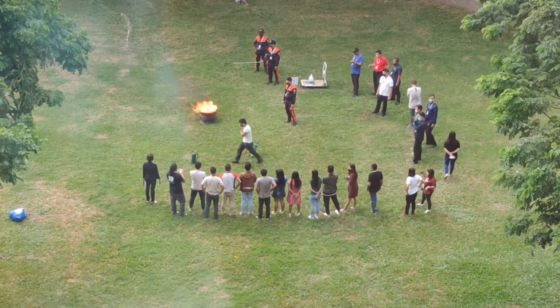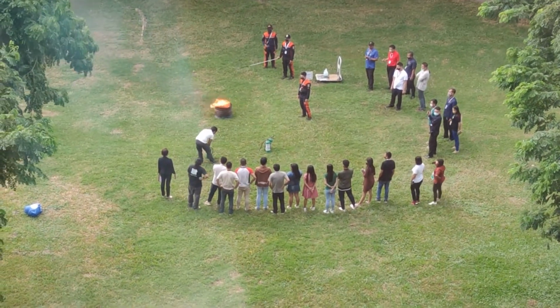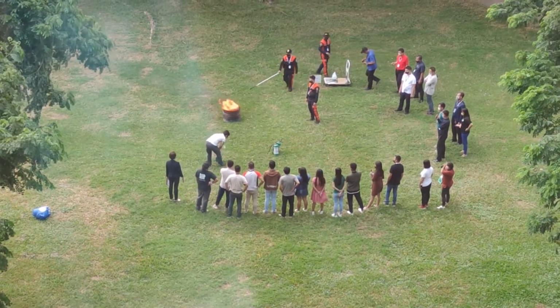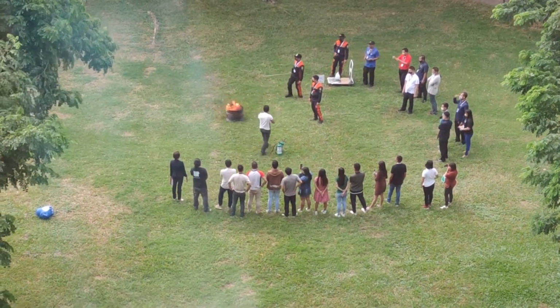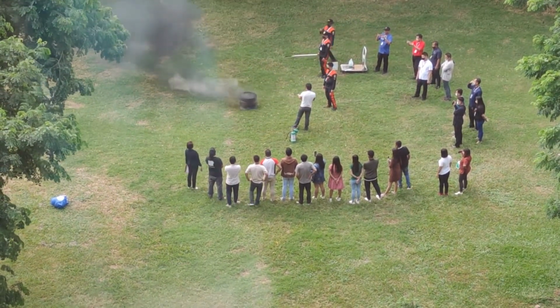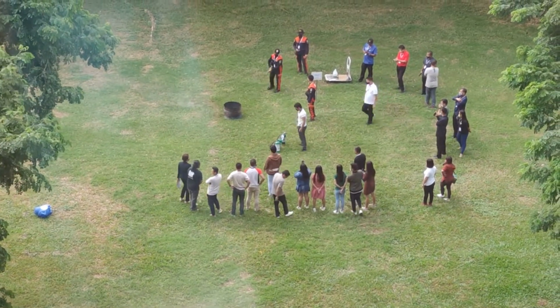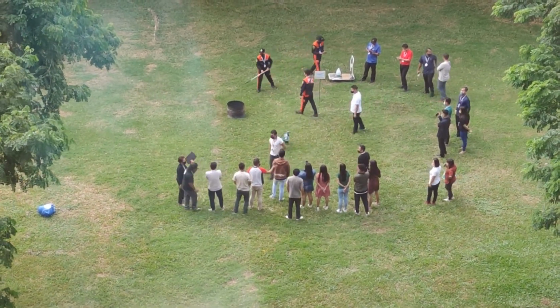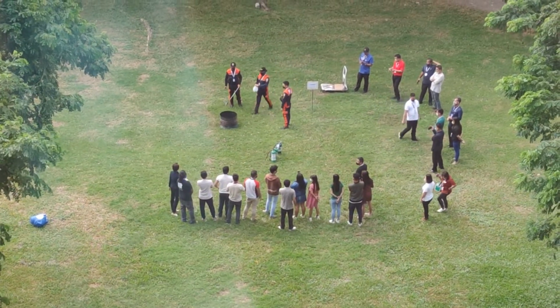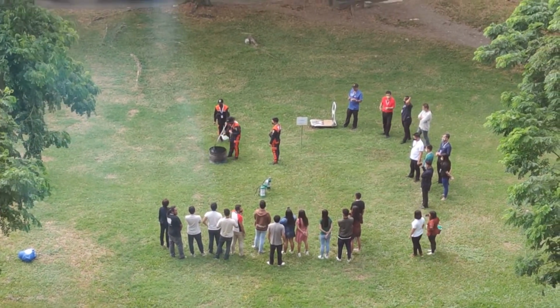Some extinguishers may have a button or other means of activation. Sweep from side to side. While you are aiming at the base of the fire, you should sweep back and forth until the fire is extinguished. If the fire reignites, repeat the process. Remember additional safeguards. Keep your back to an exit so that there is a viable means of retreating from the fire. Stand at least 8 feet from the fire and begin PASS. If the fire does not extinguish immediately, leave the fire.